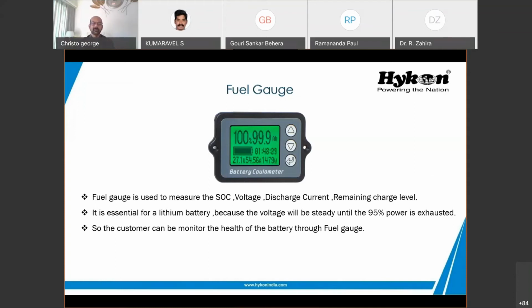A fuel gauge is used to measure the SOC, voltage, discharge current, and remaining charge levels. Sometimes this is fixed on the battery itself, because with a lead acid battery we cannot check the voltage and tell if the battery is full or not. So some customers ask us to fix this fuel gauge into the battery itself, and we provide that for many customers. It is essential for a lithium battery because the voltage stays steady until 95% of the power is exhausted, so we cannot tell the status otherwise. The customer can monitor the health of the battery through the fuel gauge.